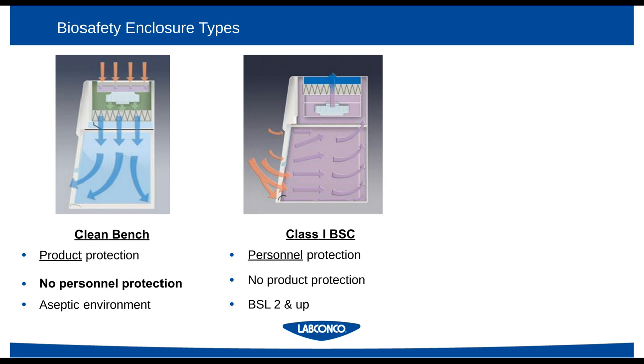On the other hand, there are negative pressure containment options out there for biological hazards. These are typically referred to as Class I BSCs, as defined by the CDC's BMBL. At the same time, also a more simplistic enclosure, providing just personnel protection for a user, so they're able to contain biohazards and other materials with particulates, but they offer no protection from outside contamination or cross-contamination in the enclosure. So for sensitive assays that require aseptic conditions, these can be problematic.